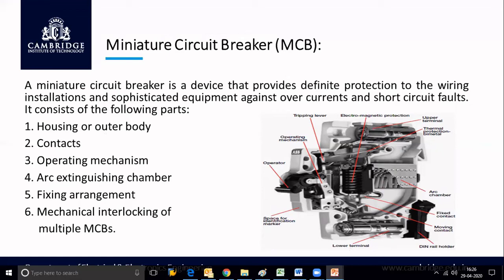Next, contacts. The contacts of the circuit are very, very important. Here you can see the red mark. One is known as the fixed contact and one is known as the moving contact. So in an MCB there are always two types of contacts: one contact is fixed, one contact is moving. Under normal operating conditions, both the contacts will be closed, touching each other.